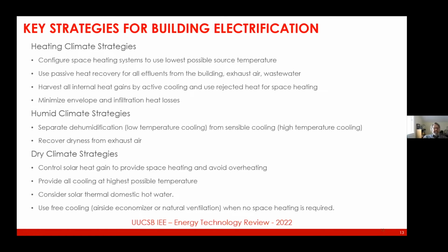So that's a very significant decrease in the amount of energy required to do the same amount of cooling, all because we're cooling at the appropriate temperature. And also in humid climates, recovering the dryness from the exhaust air. So enthalpy wheels that recover dryness from the exhaust air to partially dehumidify the incoming ventilation air.